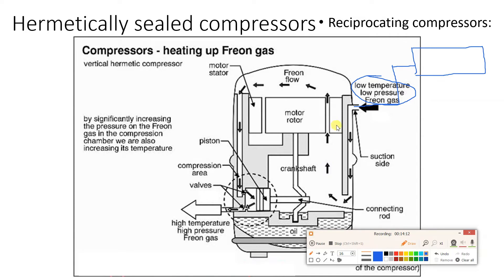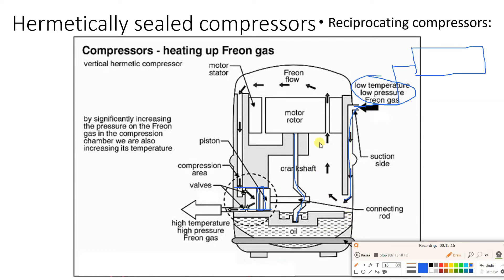A large amount of heat is generated because of the reciprocating motion. The motor operates the connecting rod, which moves the piston inside the cylinder. The suction low temperature, low pressure refrigerant enters from one side, and it picks up heat from the oil. This oil is required for lubrication due to the reciprocating motion. The oil provides lubrication and picks up heat generated between the piston and cylinder, while the refrigerant cools the oil and keeps the motor cool.